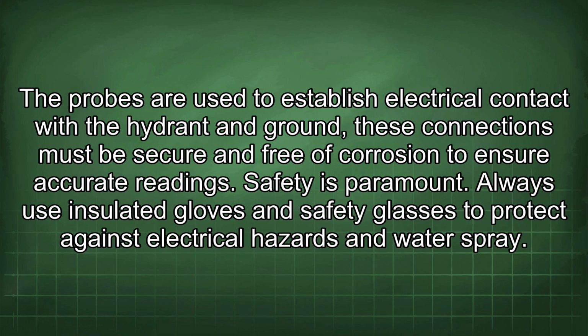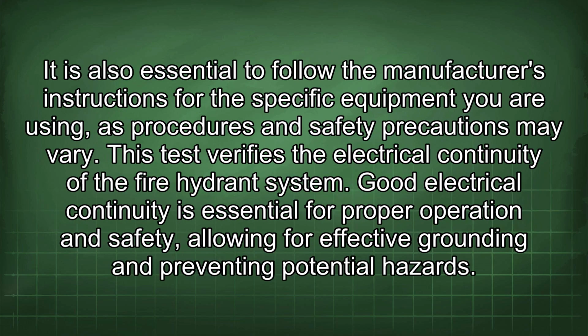Safety is paramount. Always use insulated gloves and safety glasses to protect against electrical hazards and water spray. It is also essential to follow the manufacturer's instructions for the specific equipment you are using, as procedures and safety precautions may vary. This test verifies the electrical continuity of the fire hydrant system. Good electrical continuity is essential for proper operation and safety, allowing for effective grounding and preventing potential hazards.